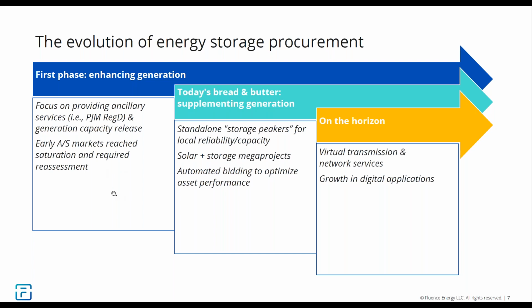The second trend is a lot of growth around solar plus storage mega projects, pairing solar with storage, whether in AC coupled capacities where they don't need to be co-located but can share some benefits from sharing the same land and grid connection, or DC coupled systems where you take advantage of co-locating those assets to oversize the PV to inverter ratio and gather and store more power from a larger solar installation to on-site storage.